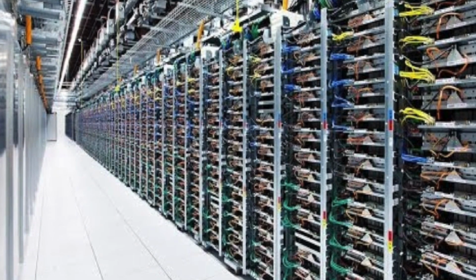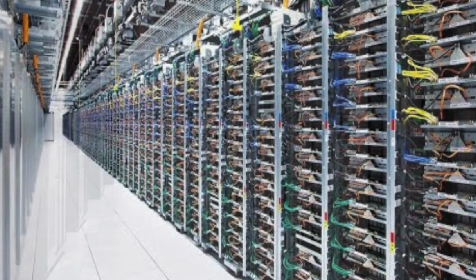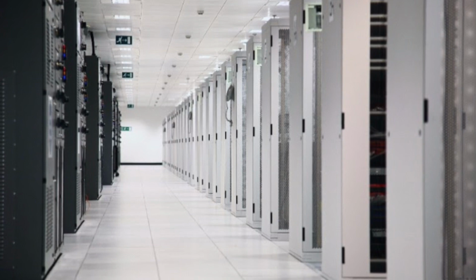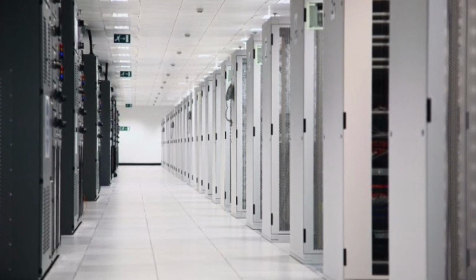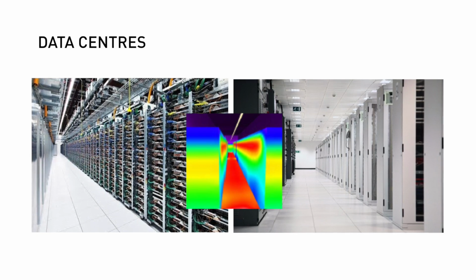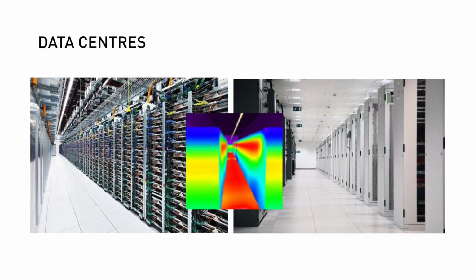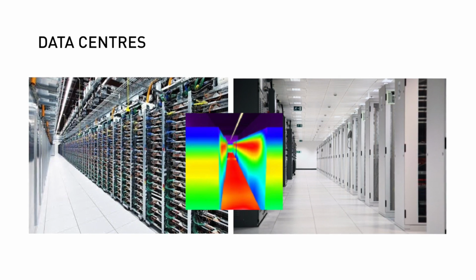Now, data centres generally marry up very, very well to a linear format lighting. Linear racks. Exactly. And therefore also good vertical illumination for the engineers, good horizontal illumination if you've got a tenant space and you need to show the space off as well. But some data centres will utilise a 600 by 600 ceiling grid. The disadvantage to this is that the 600 grid doesn't necessarily line up every time with where the data centre racks are positioned, and they're also limited by the venting within the space or the fire detection system as well, which is very key to a data centre. So whilst you will see 600 by 600 layouts, they generally are not very well optimised at the space, and it's better to go down the linear route if at all possible.